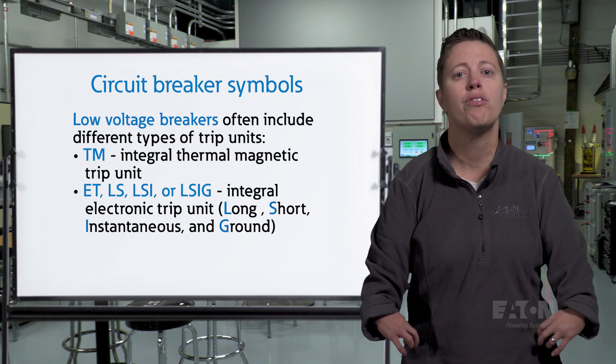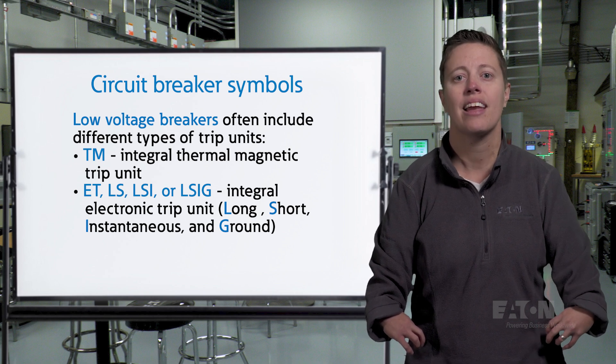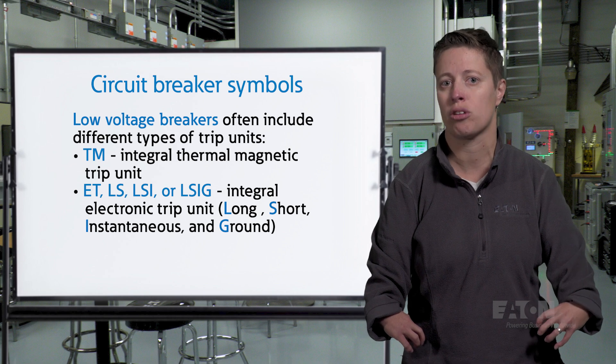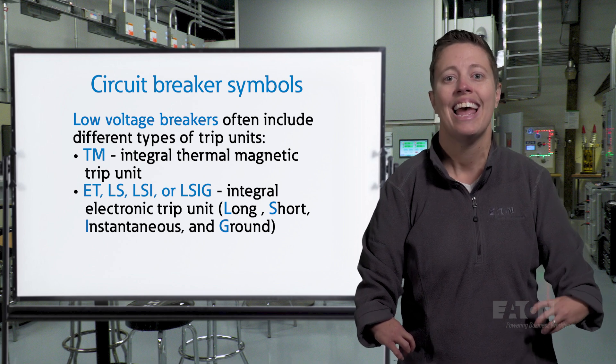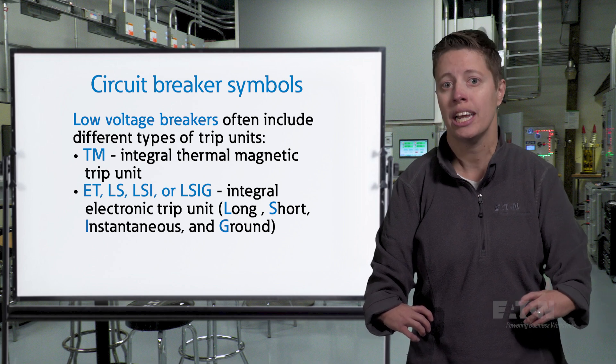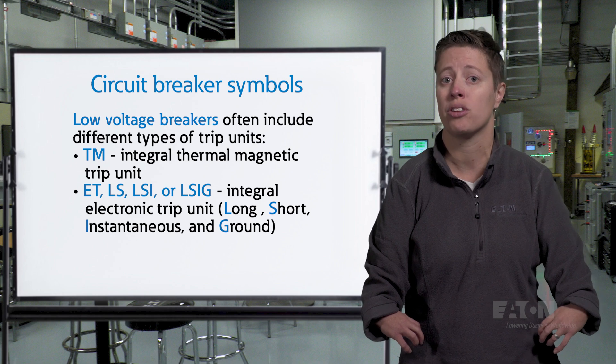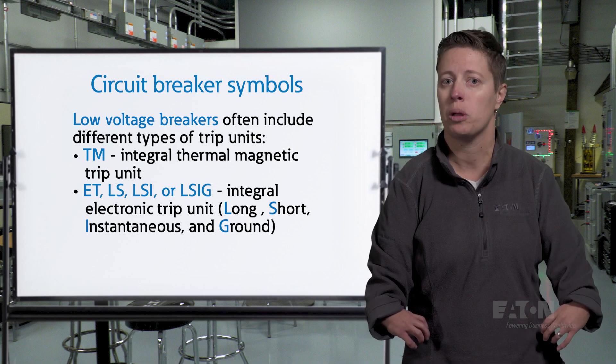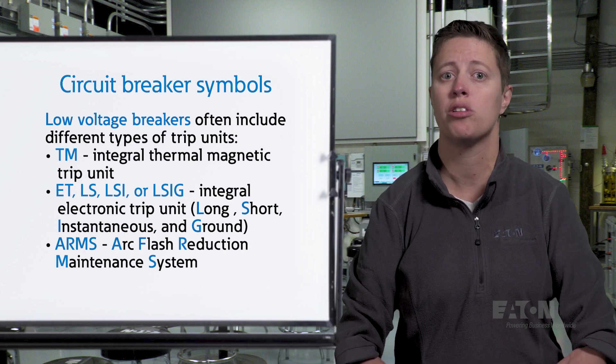Circuit breaker symbols often include a lot of additional notes and abbreviations that describe how the breaker operates. Low voltage breakers include integral trip units in one of several types. TM indicates the breaker has an integral thermomagnetic trip unit. ET, LS, LSI, or LSIG indicate the breaker has an integral electronic trip unit. The L, S, I, and G refer to the types of protection provided by the trip unit: long, short, instantaneous, and ground. Not every electronic trip unit provides every type of protection. The circuit breaker may also note ARMS protection is to be included.